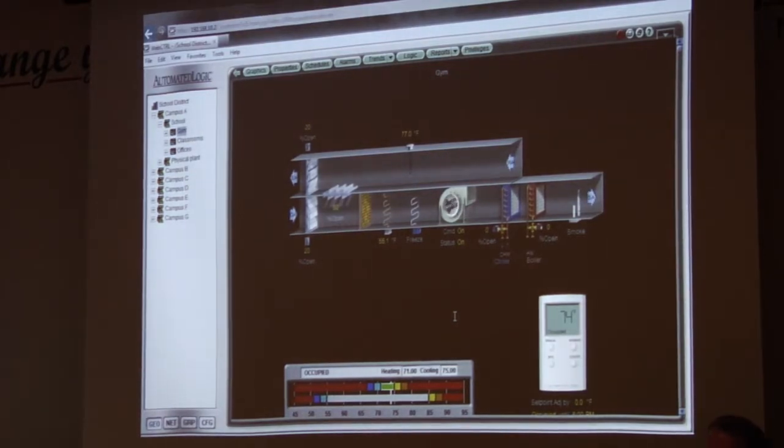And whatever we put on the first screw, usually 24 volts, when we do a dry contact, that's what comes out the second screw, right? So if you come through all of our outputs, you'll see there's a daisy chain of power. We send 24 volts on every input, and then whichever relay we want to turn on, that comes on the output. But anything could short those screws.